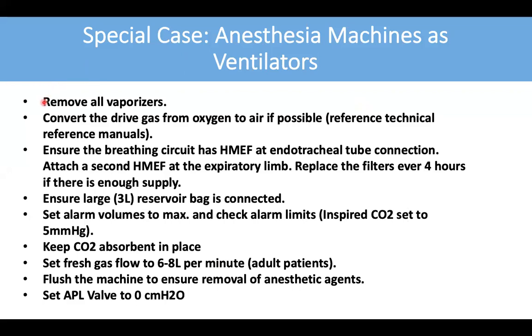You will begin by removing all the vaporizers on the anesthesia machine. If possible, you will convert the drive gas from oxygen to air. Not all anesthesia machines are capable of doing this easily. If you reference the technical service manuals, they will give you detailed steps on how you can change the drive gas on each anesthesia machine.